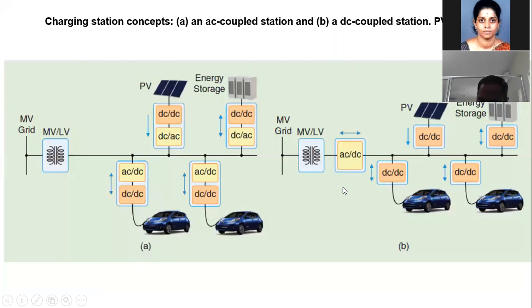What you must ensure is that in a smart grid environment, you are not supposed to increase or decrease the power drawal just like that. There must be an allowed power ramp, a fixed power ramp up or ramp down that you maintain with the help of a hybrid energy storage system, MPPT control, and other things. For example, for a minute you cannot go beyond 5 kilowatt - from the last minute to this minute you can only increase or decrease by 5 kilowatt.